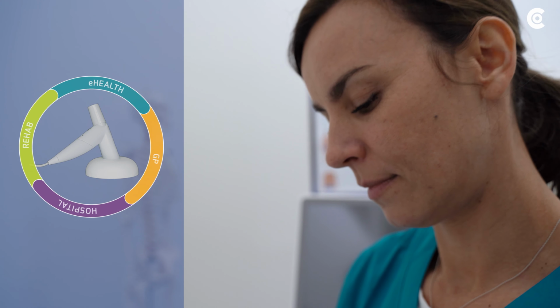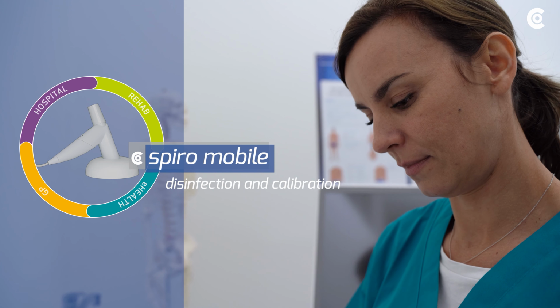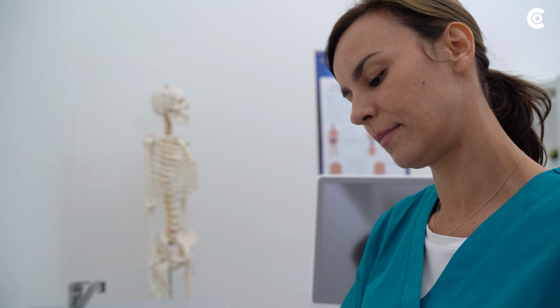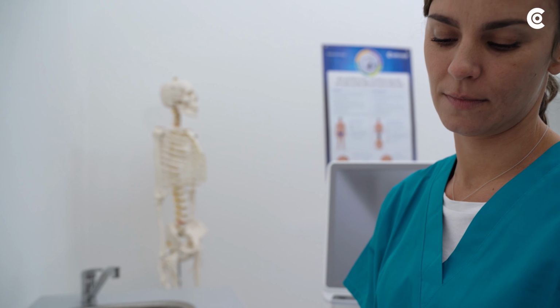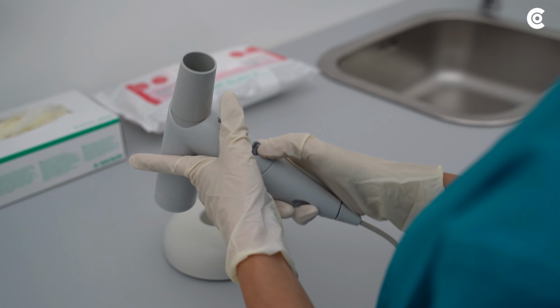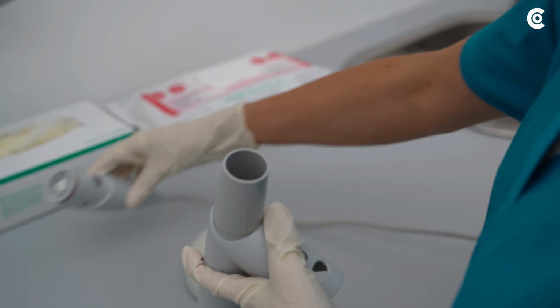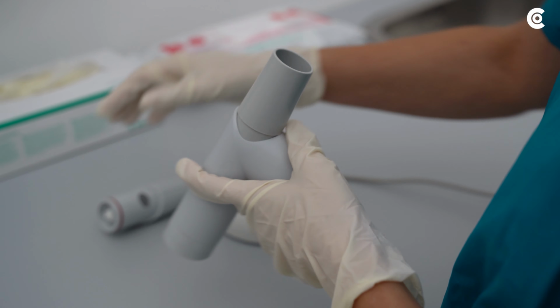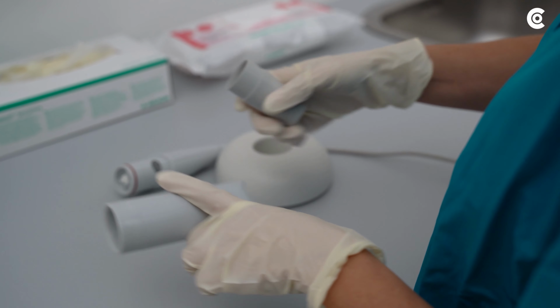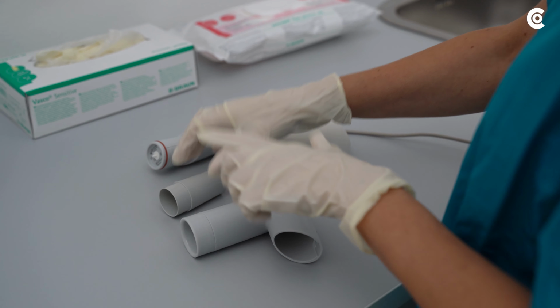The following video shows how to disinfect and calibrate Customed's Spiro Mobile correctly. Disassemble the Spiro Mobile. Remove the measuring head from the handle by pressing the release button and pulling the measuring head upwards. Then pull the mouthpiece off the measuring head.